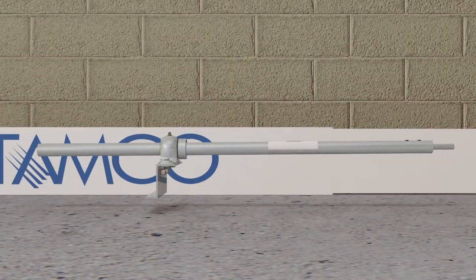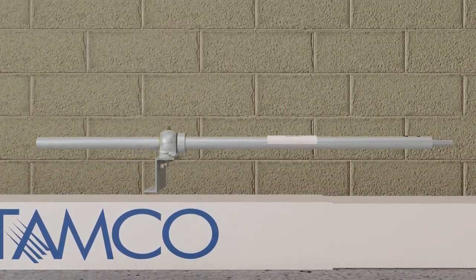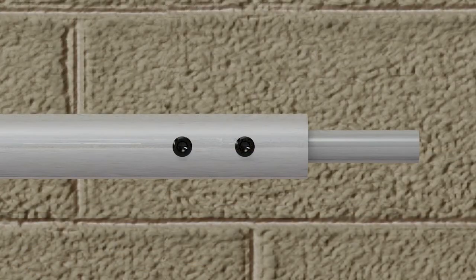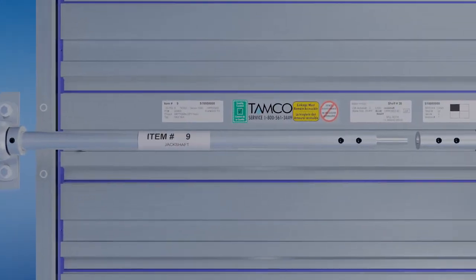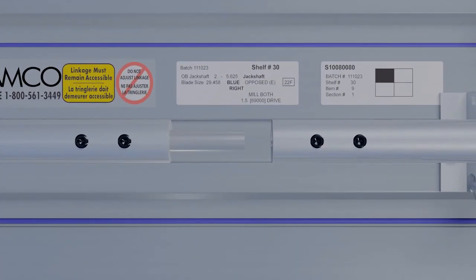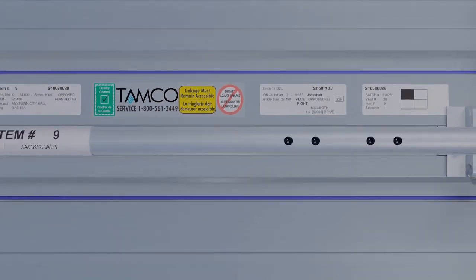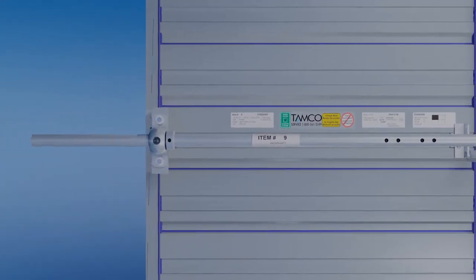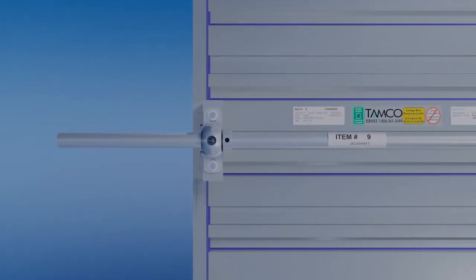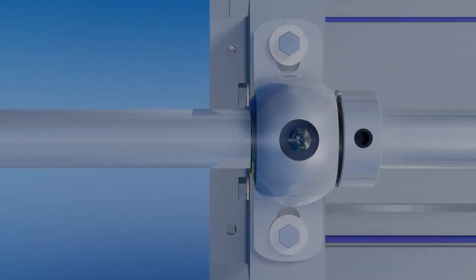The 1-inch diameter shaft that is part of the side bracket assembly is supplied with an internal hexagonal rod that is used to make the internal connection to the bridge bracket assembly. Insert the hexagonal rod into the left side of the shaft within the bridge bracket assembly. Place the side bracket so that the holes align with the pre-drilled holes on the left damper frame.